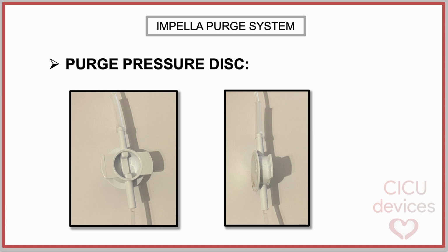In terms of operating principle, purge fluid is delivered from the console into the catheter under variable flow rates. As purge pressure rises or falls, the purge pressure disc deforms proportionally. This deformation is detected by the console's sensing mechanism, which automatically increases or decreases purge flow to maintain pressure within the desired range. This process is fully automated and continuously active during device operation.